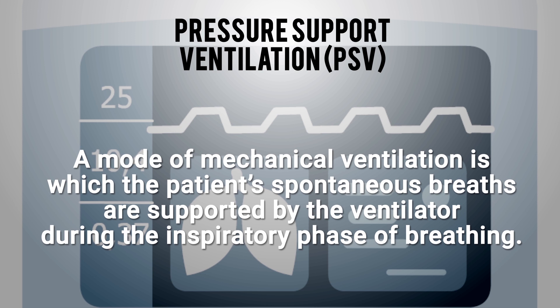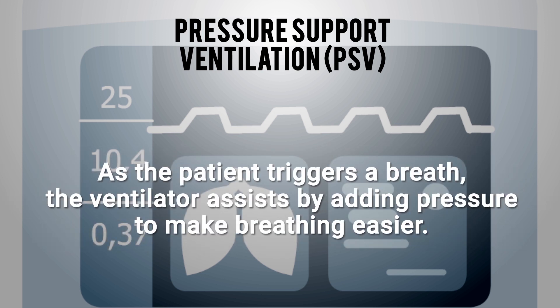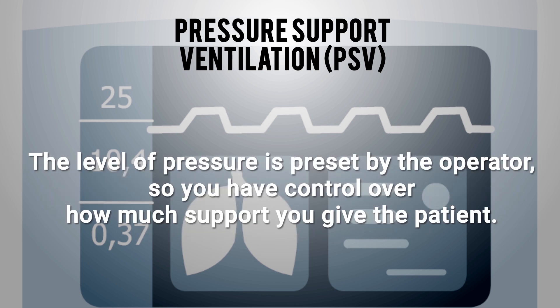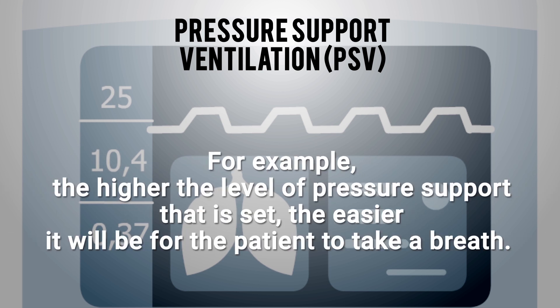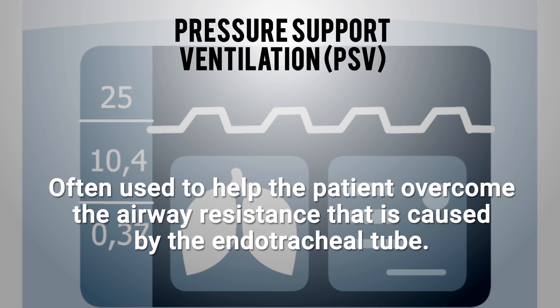PSV, or Pressure Support Ventilation, is a mode in which the patient's spontaneous breaths are supported by the ventilator during the inspiratory phase. As the patient triggers a breath, the ventilator assists by adding pressure to make breathing easier. The level of pressure is preset by the operator — the higher the pressure support set, the easier it is for the patient to breathe. In PSV, breaths are flow-cycled and pressure-limited. Pressure support is often used to help the patient overcome airway resistance caused by the endotracheal tube.